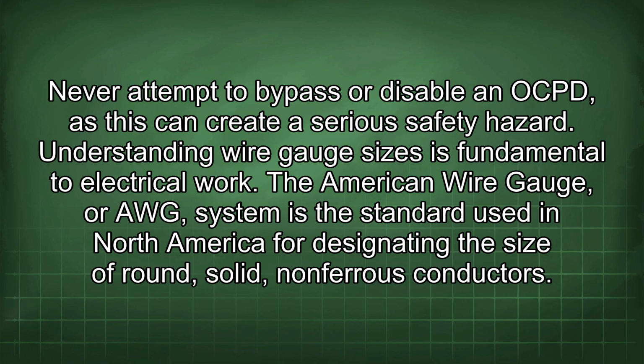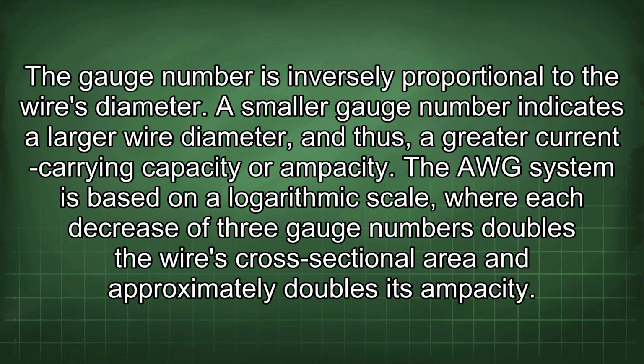Understanding wire gauge sizes is fundamental to electrical work. The American Wire Gauge, or AWG, system is the standard used in North America for designating the size of round, solid, non-ferrous conductors. The gauge number is inversely proportional to the wire's diameter. A smaller gauge number indicates a larger wire diameter, and thus a greater current carrying capacity, or ampacity.